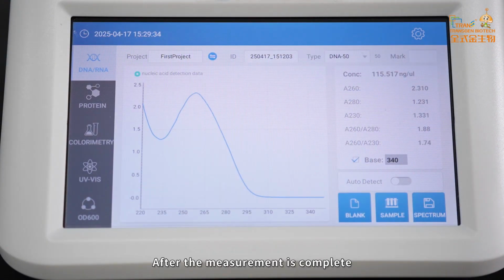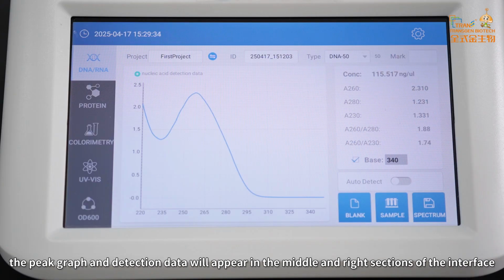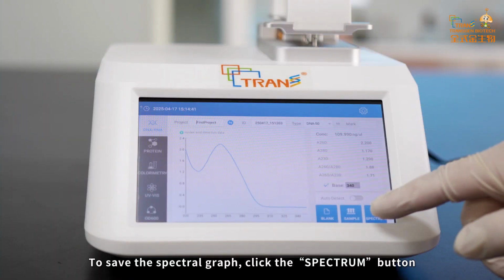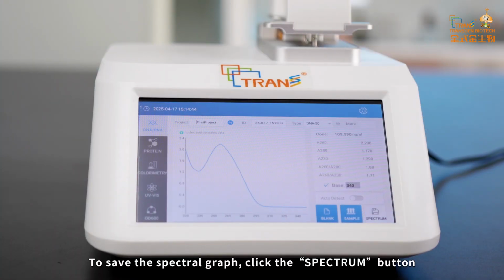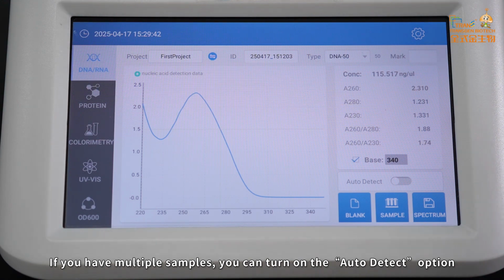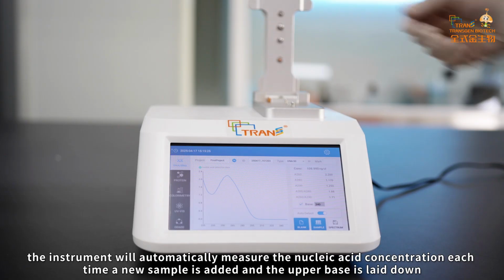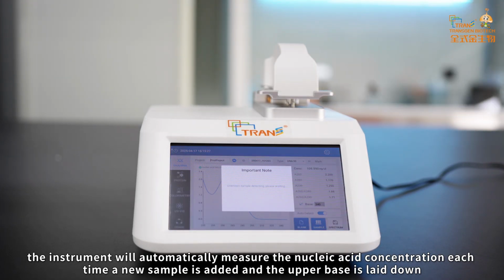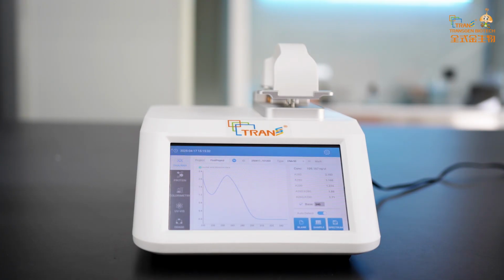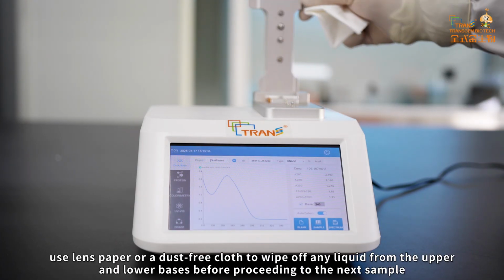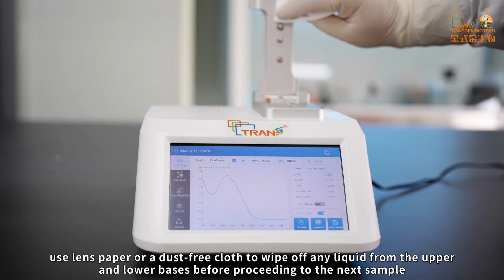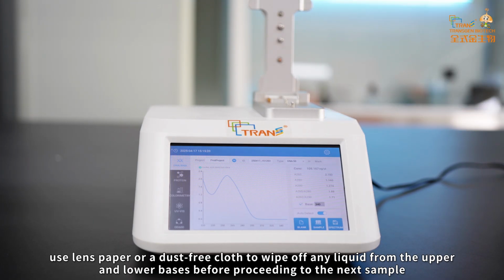After the measurement is complete, the peak graph and detection data will appear in the middle in the red section of the interface. To save the spectrograph, click the Spectrum button. If you have multiple samples, you can turn on the auto detection option. With this turned on, the instrument will automatically measure the nucleic acid concentration each time a new sample is added and the upper base is laid down. After measuring each sample, use lens paper or a dust-free cloth to wipe off any liquid from the upper and lower bases before proceeding to the next sample.